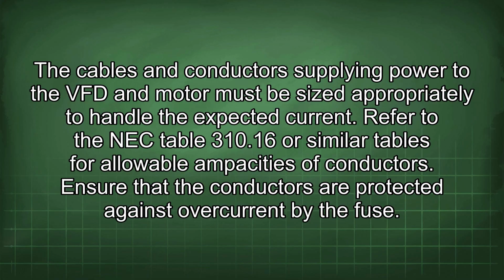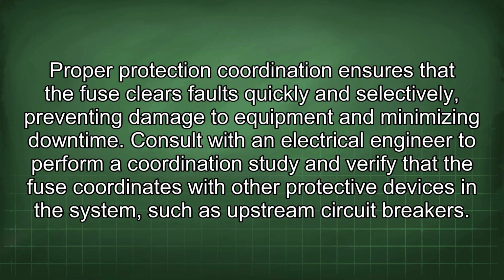The cables and conductors supplying power to the VFD and motor must be sized appropriately to handle the expected current. Refer to the NEC Table 310.16 or similar tables for allowable ampacities of conductors. Ensure that the conductors are protected against overcurrent by the fuse. Proper protection coordination ensures that the fuse clears faults quickly and selectively, preventing damage to equipment and minimizing downtime.